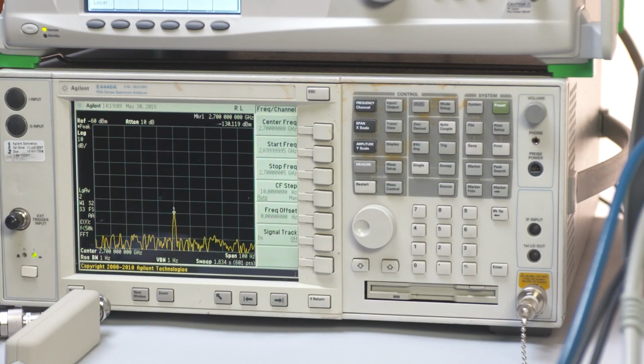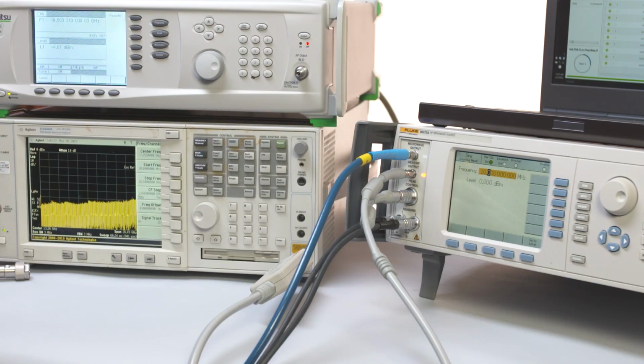The full calibration procedure takes about 1 hour and 10 minutes with minimal connection changes and minimal operator interaction. This is about 12 hours faster than the same calibration done manually and about twice as fast as the manufacturer's own calibration system. We are including a timer so you can see how long it takes to run this procedure.